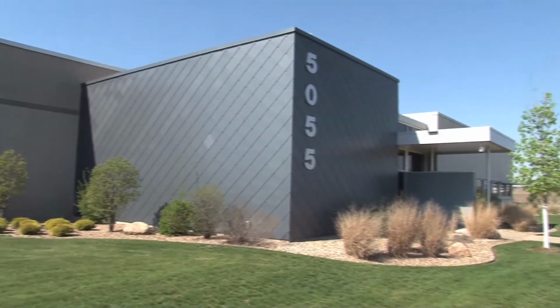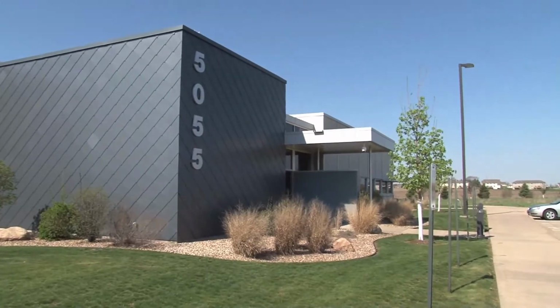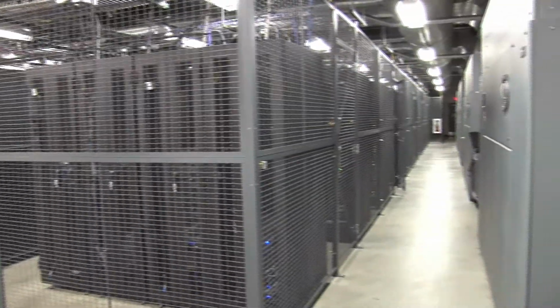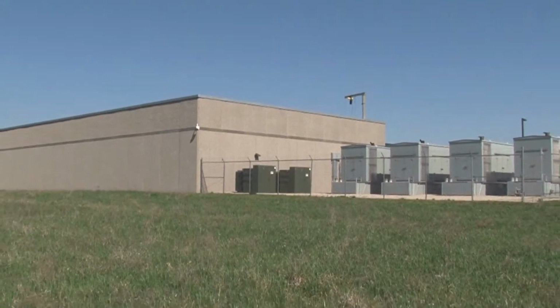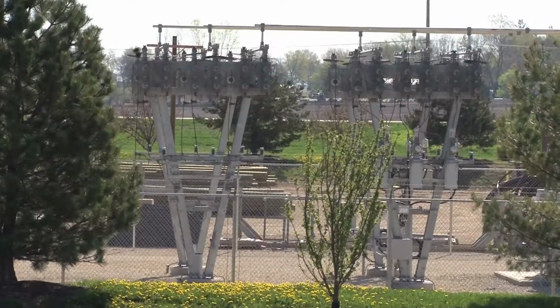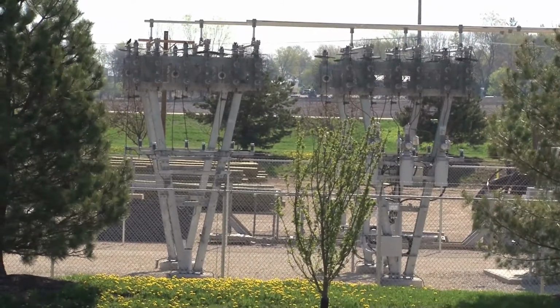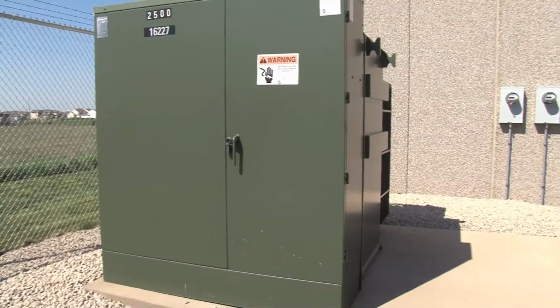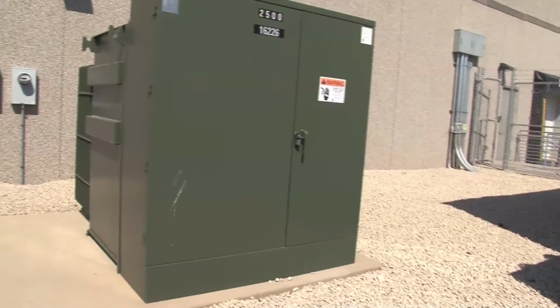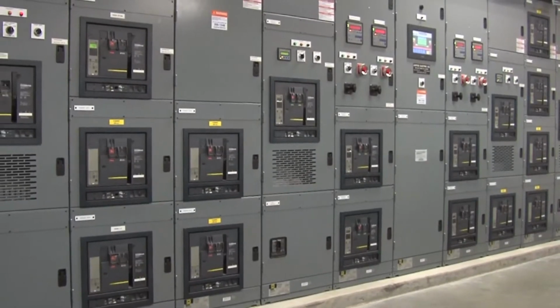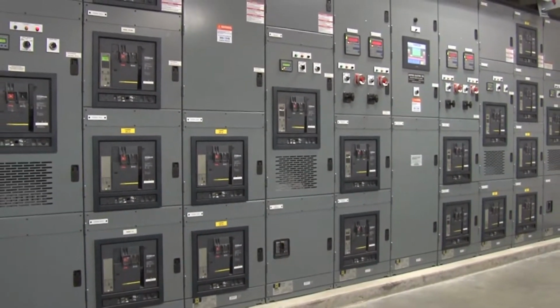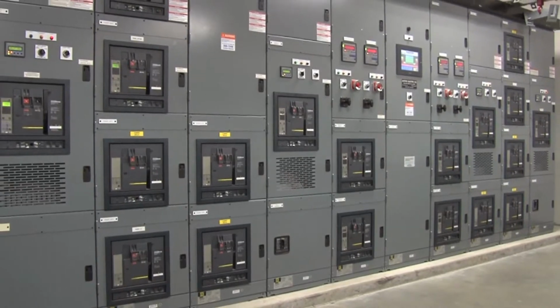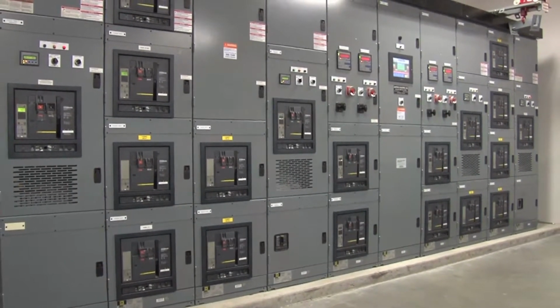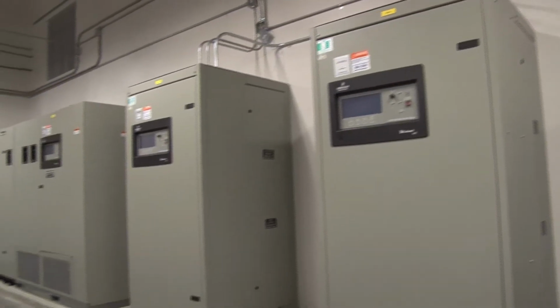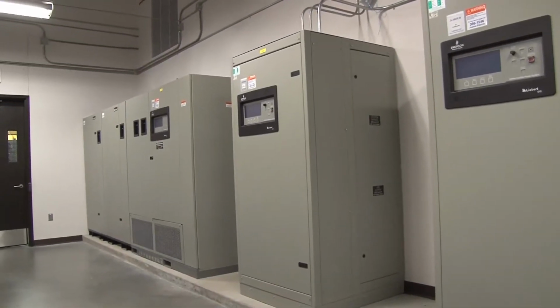Involta Marion is 18,300 square feet. We have 300 racks at 2.7 kW per rack. The building is supplied by 2 feeds from the utility service. That comes from 2 different substations through independent 2,500 kVA transformers, each capable of running the entire facility. And then we go into a switchboard that allows for 4 diesel generators to interact with those 2 independent power sources. And then we go into 2 900 kVA isolated dual UPS buses to each of the equipment racks.